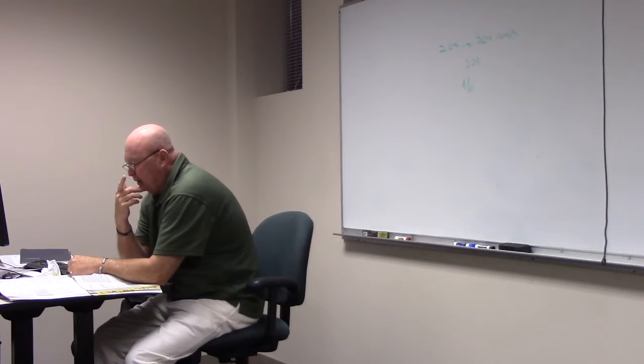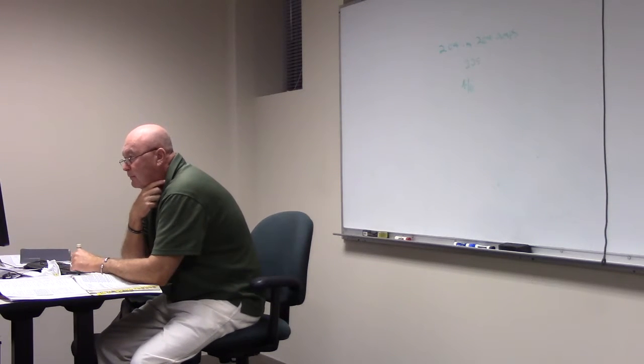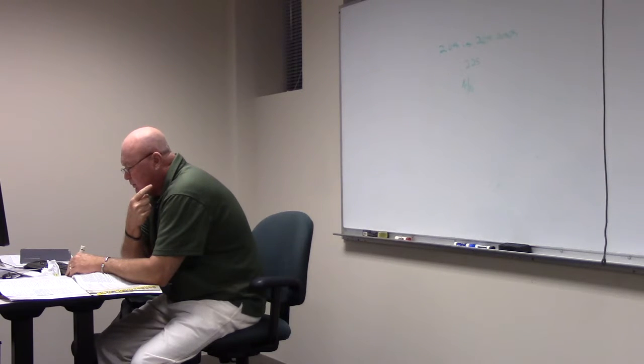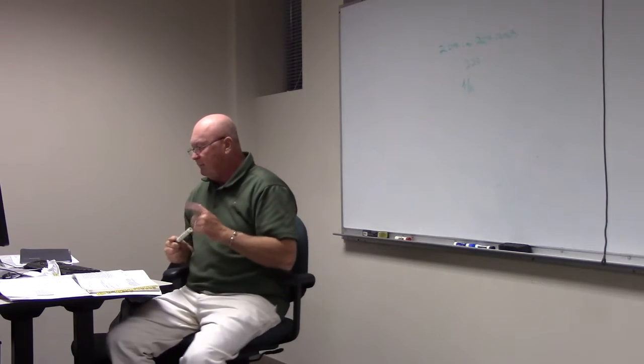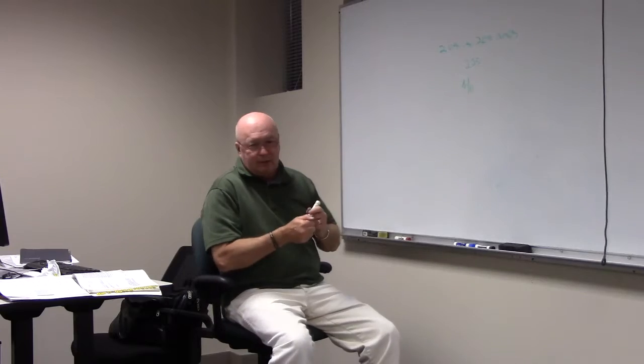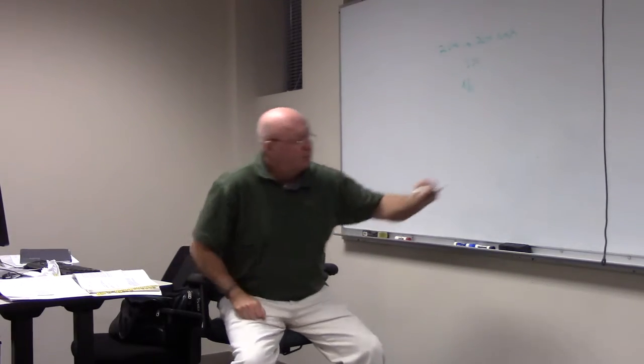All right. So that's what we've done, step number 10 there. See there, step number 10. But there's a transformer that feeds all this. So look at step 11 in your book. The transformer is sized to accommodate the computed load of 73,563, which is what we came up with. Select the overcurrent device for the transformer. We already got that. How much was it? 73,563?